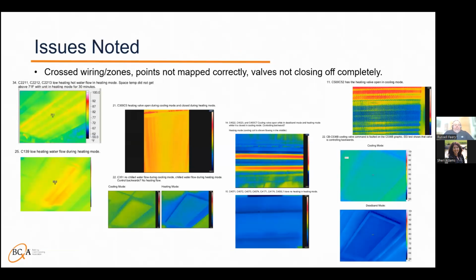Now, some issues noted. During our initial testing, we found that they had some crossed wiring in zones, points that were not mapped correctly, valves not closing off completely. And we've got some pictures here that we'll go over kind of left to right. And it kind of highlights the need of why you have to have an infrared camera to properly test the system.